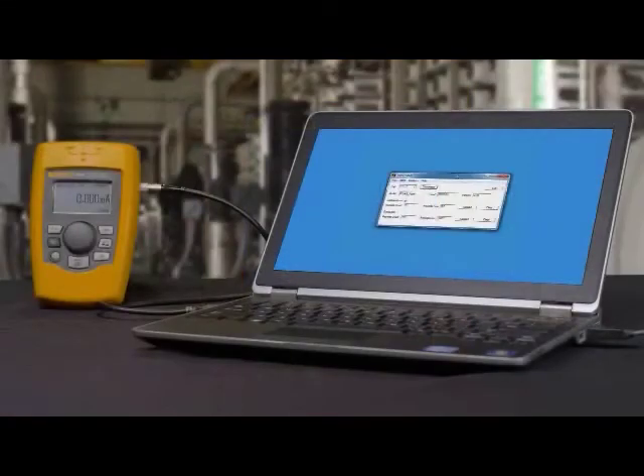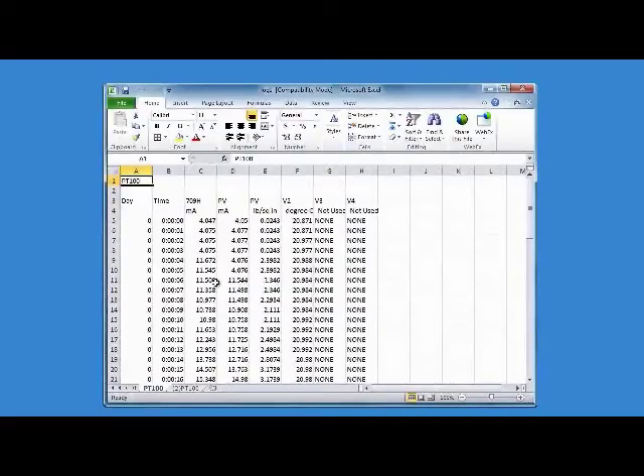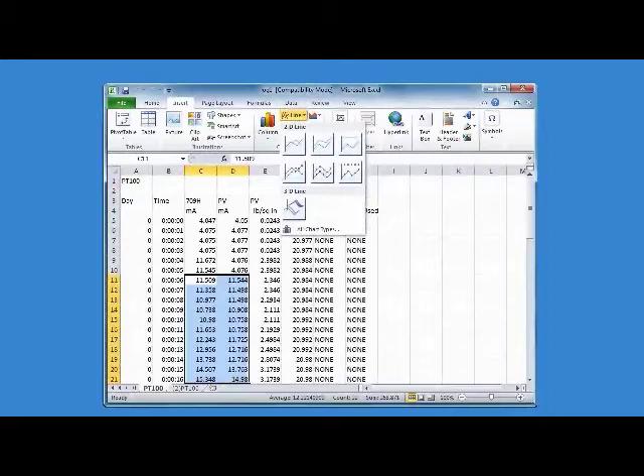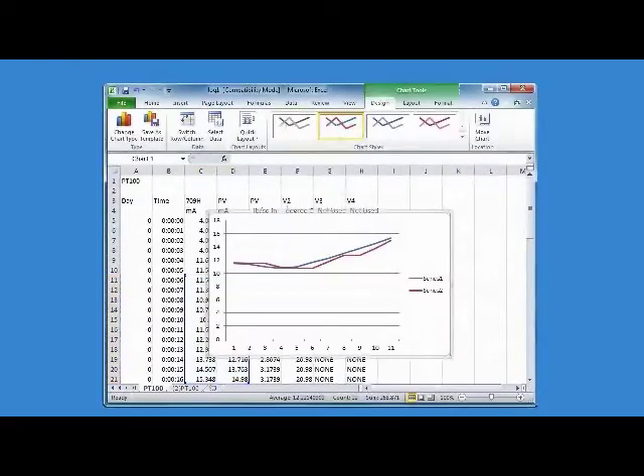Another unique feature in the 709H is the logging feature. Working with the optional 709 Track software, you can log both the measured milliamp values and the HART parameters in a smart transmitter over time. This logging feature is a great diagnostic tool for loop tuning and troubleshooting.